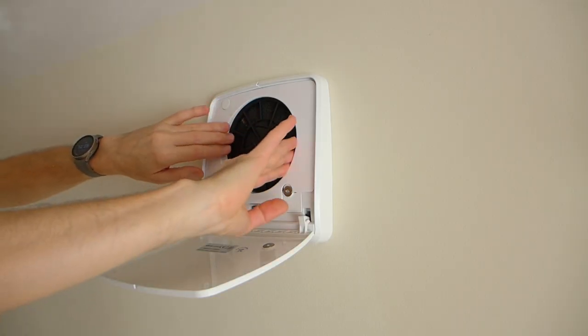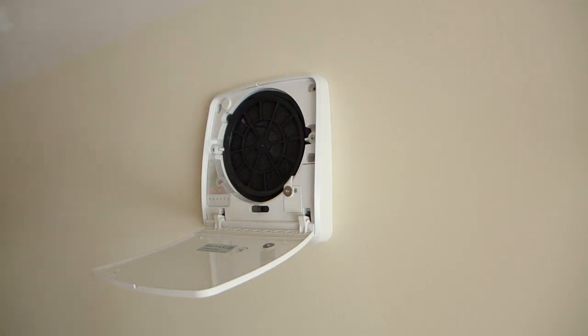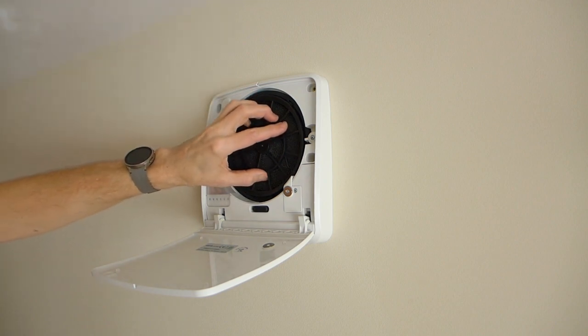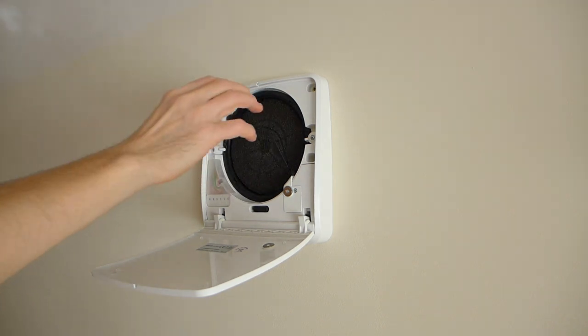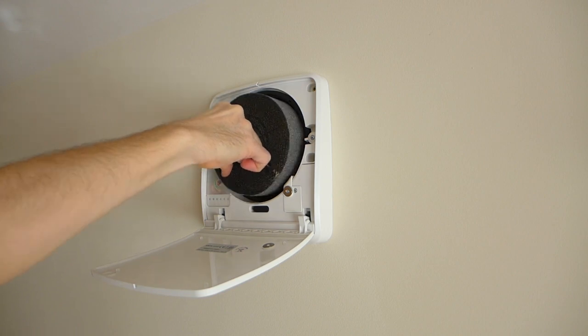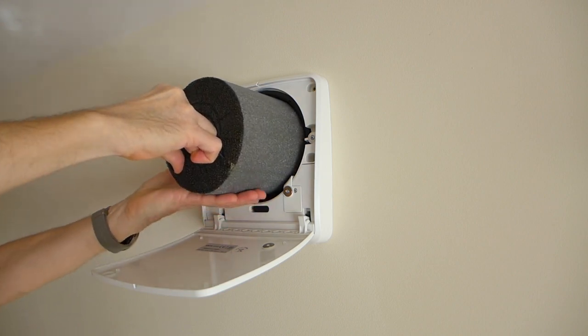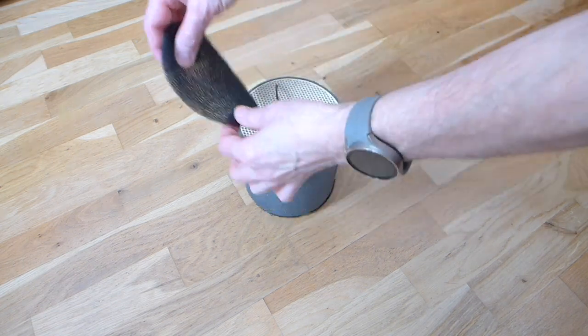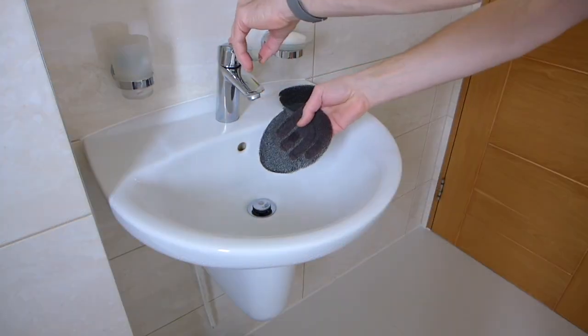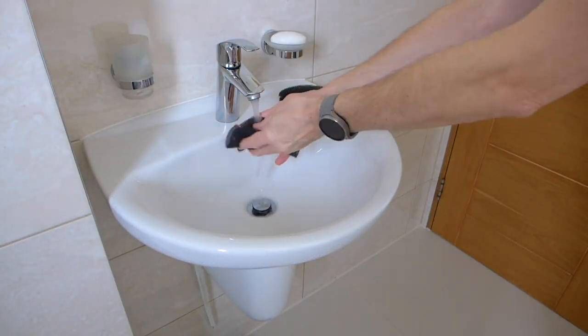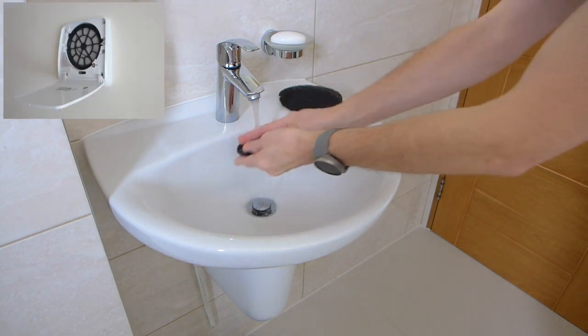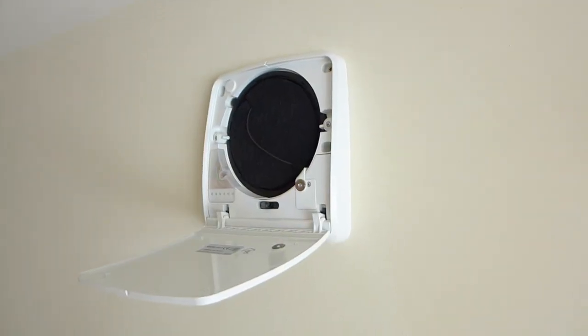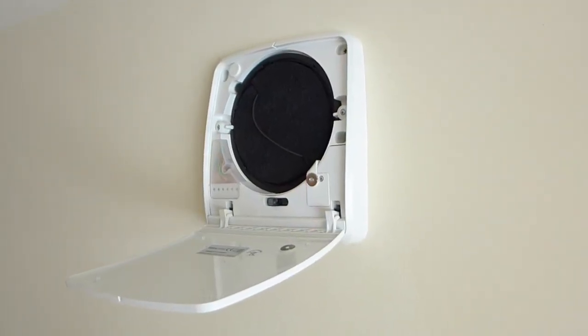Once the flap is opened, remove the optional cover. Turn the retaining grille anti-clockwise to disengage and remove it. Grab the handle and slide out the heat exchanger with the filters, supporting the weight with your other hand. Remove both filters and wash them. This applies to the supplied G3 standard filters as well as the optional M5 pollen filters. If your filters are activated carbon filters, do not wash them, but replace them with new ones.